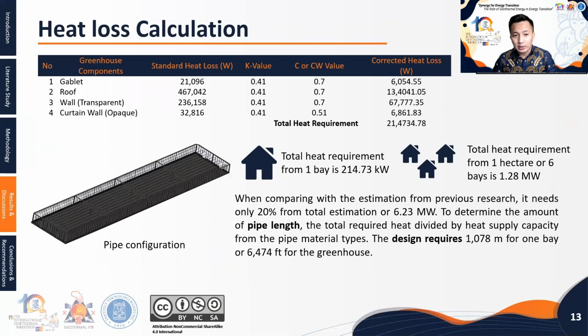For the heat loss calculation, the total heat requirement that has to be fulfilled by the geothermal fluid is 200 kilowatt. For the total greenhouse, it needs 1.3 megawatt. This value is only 20% of the total estimated resource. To determine the pipeline, the total required heat is divided by the heat supply capacity of the pipe material types. As a result, this design requires 1,000 meters for one bay, or 6,500 for all the greenhouse.